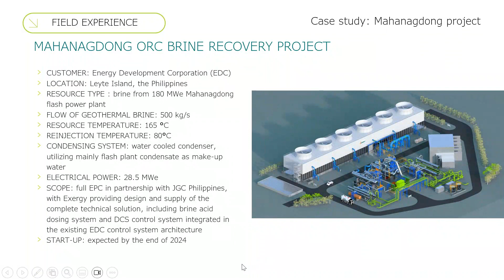In this project, it's worth mentioning that the brine composition was quite challenging for its chemical properties. In fact, especially due to the high silica content of this brine, it would be practically impossible to use the brine as-is and cool it down from 180 degrees to 80 degrees through the ORC.